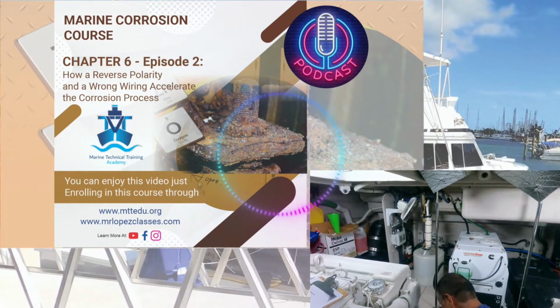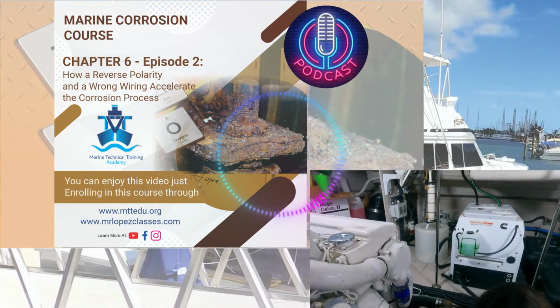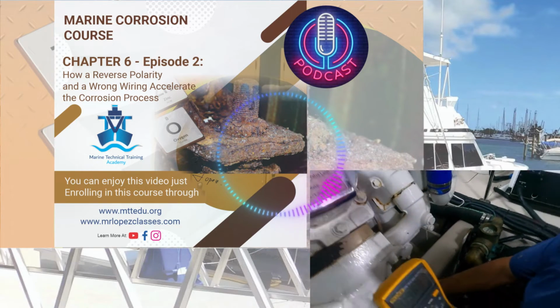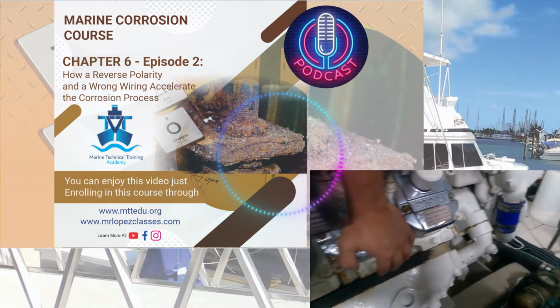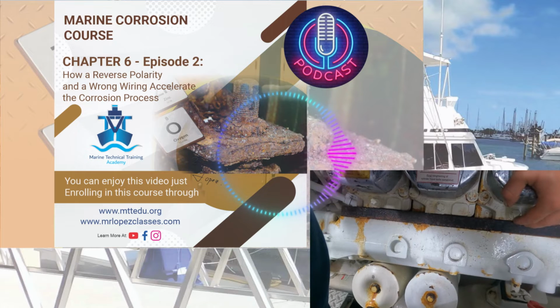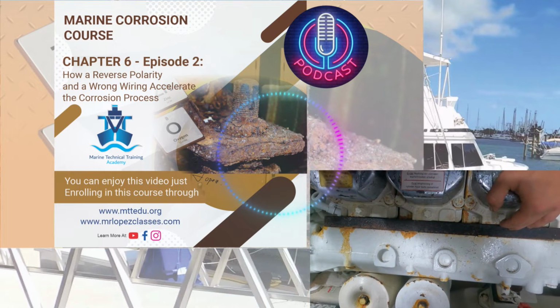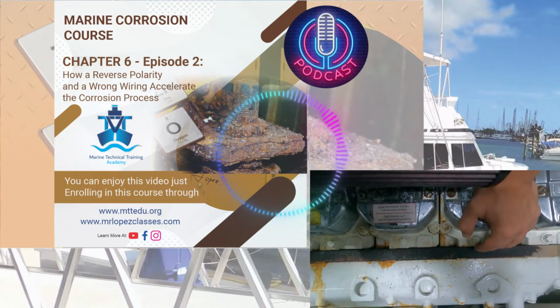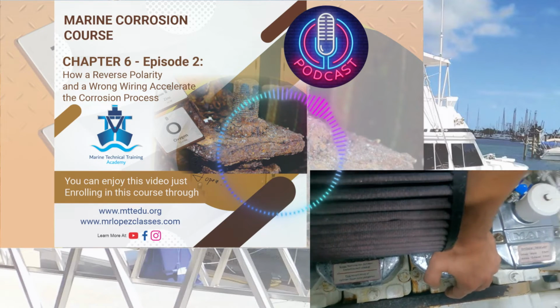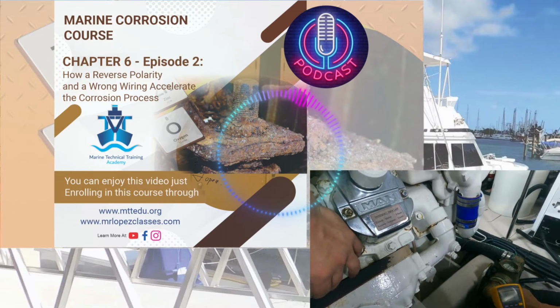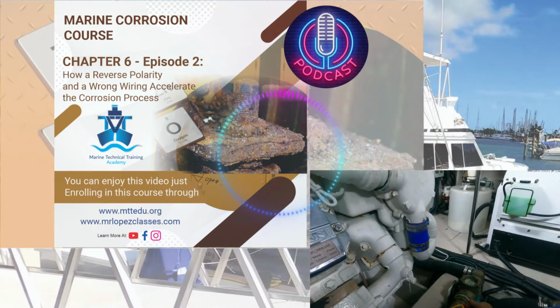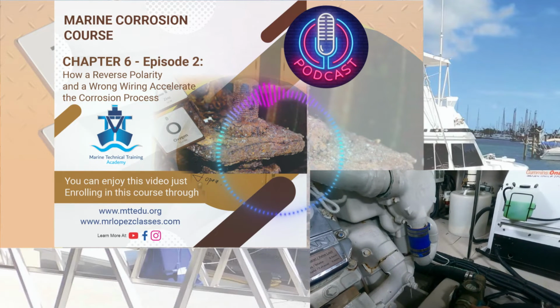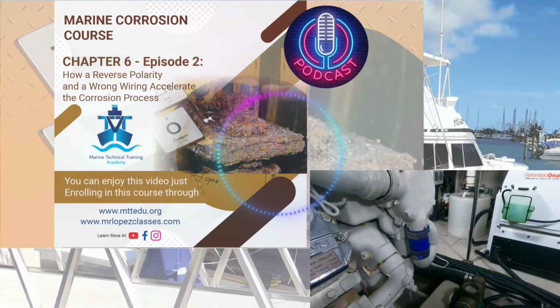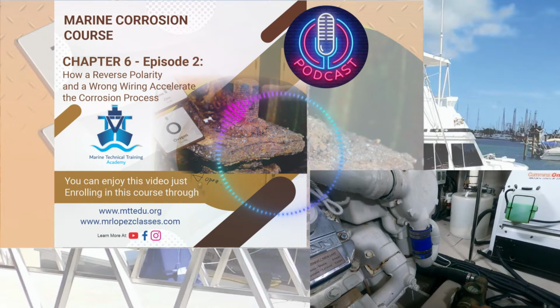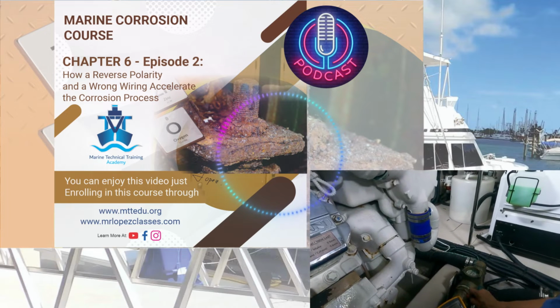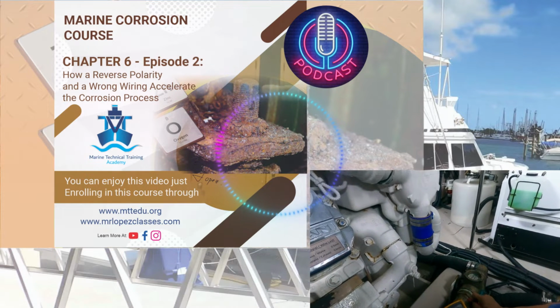You have three different sources of power in your boat. One source of power is the pedestal, the transformer on the marina. At the source of the power, on the transformer, neutral and ground are together. The same like in the generator. In the back end, where the electricity is produced on the stator or rotor, depending on the type of generators, in that board neutral and ground are connected together. After that, they go separated. And never try to put together inside of the boat, both of them.